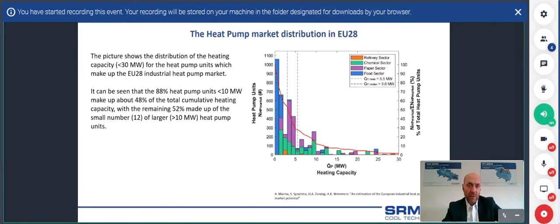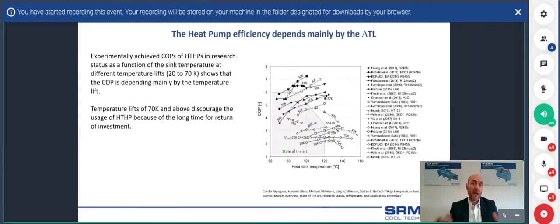So the numbers for all the heat pumps are very significant, and this is where we would like to focus, on this area with a higher demand. Another look at the market and at the state of the art at the moment is given by this graph, which shows the positioning of the laboratory or experimental systems, and positions the efficiency of the system, especially the COP, compared with the heat sink temperature, so the temperature of the condenser.